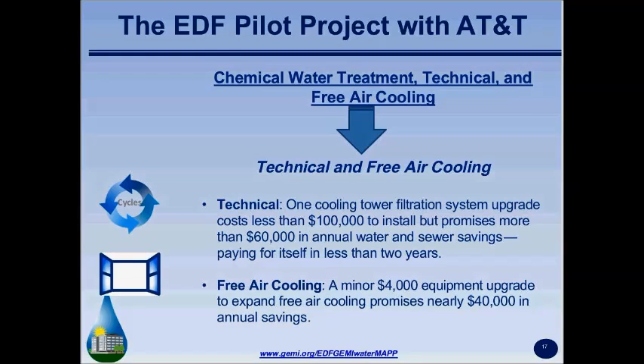AT&T, like many companies, had lots of buildings with air economizer systems installed, but over time sections of those systems had broken down and weren't operating at full capacity. Projects like repairing a damper to restore full functionality produced huge savings in dollars, water, and energy, since you no longer needed as much mechanical cooling from the chiller, which uses significant energy. It was a great opportunity providing multiple benefits for water and energy savings, and was very cost effective.